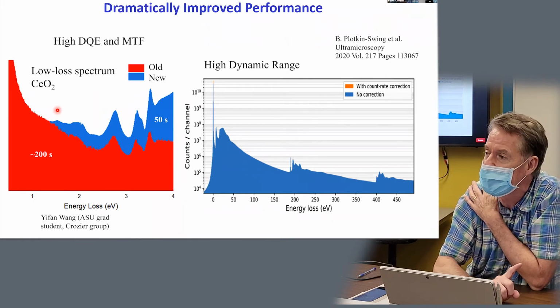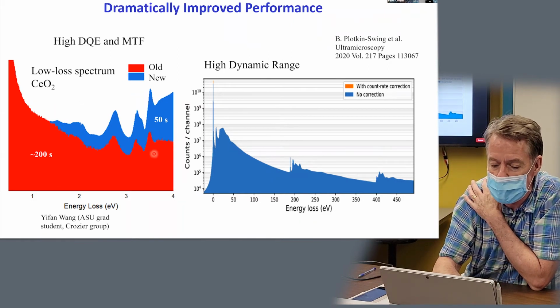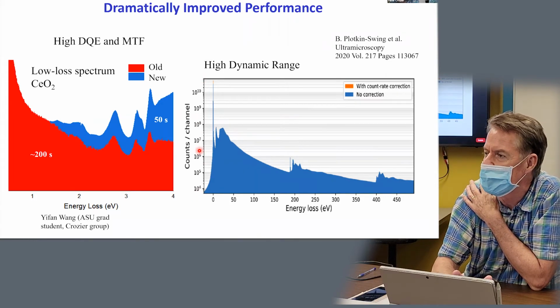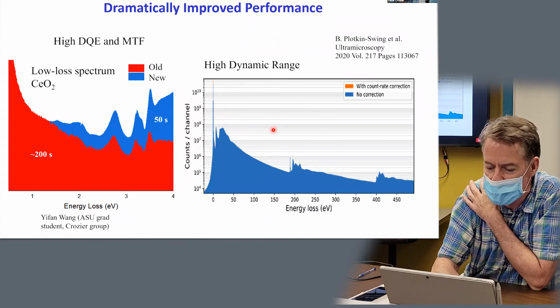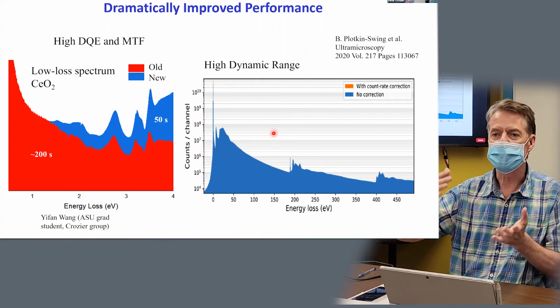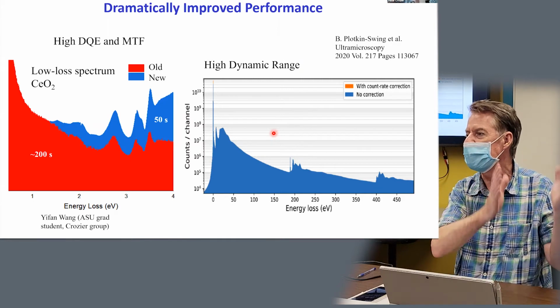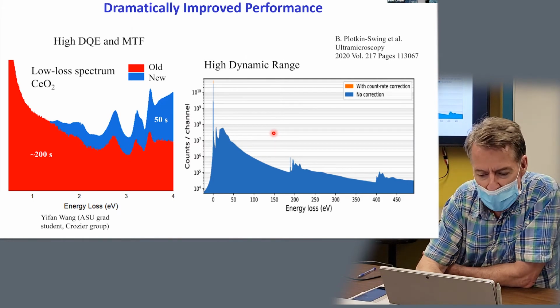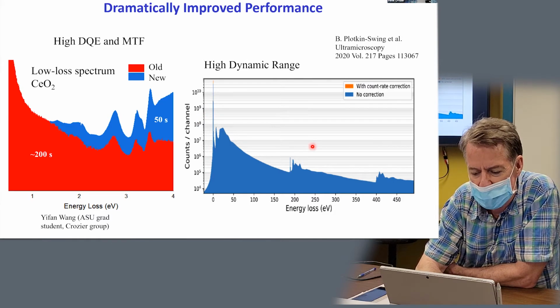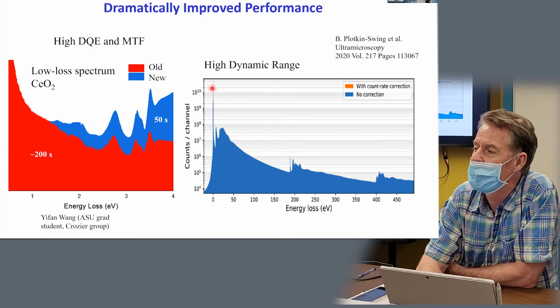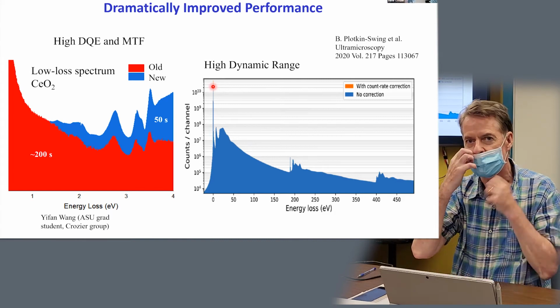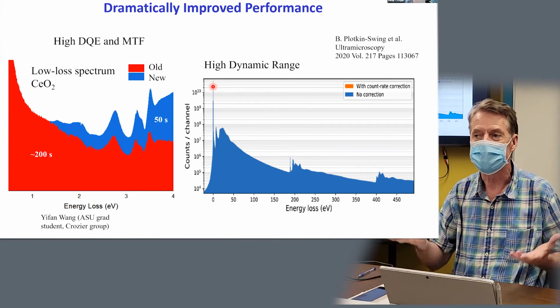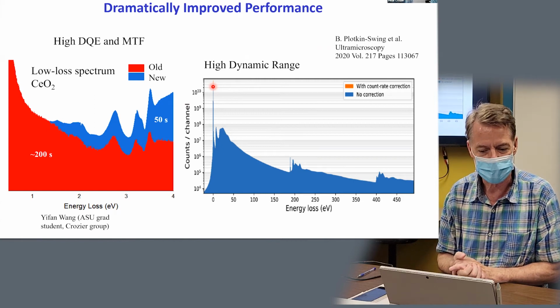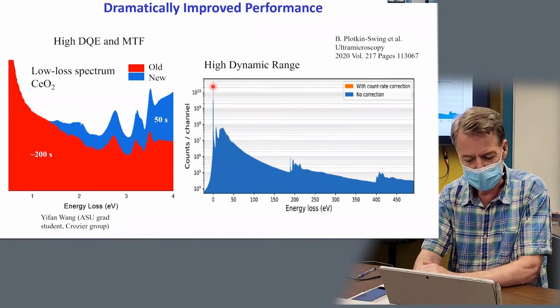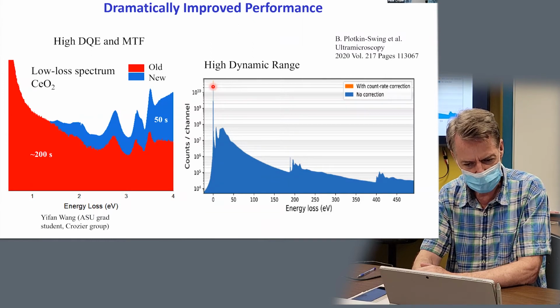The other thing about this detector, which is great, for those of you that know about spectroscopy, is that the electron energy loss spectrum typically spans about 7 orders of magnitude in terms of intensity. And usually most of our old detectors could only span 3 or 4 orders of magnitude, so we would have to record the spectrum in separate chunks. Now we can record the entire spectrum in one go and capture the entire dynamic range without any saturation effects at all. And that's really going to be fabulous for a lot of applications like elemental mapping. So I'm going to hand you back to Shize, who will go through a few more examples.